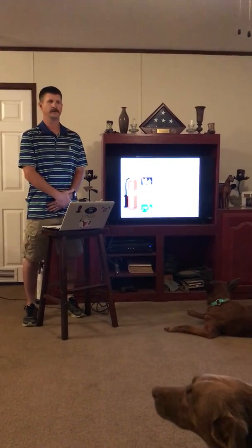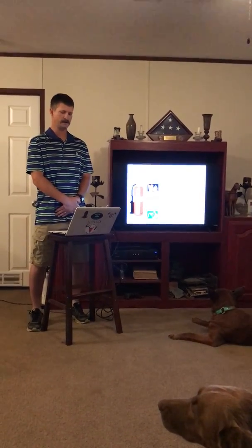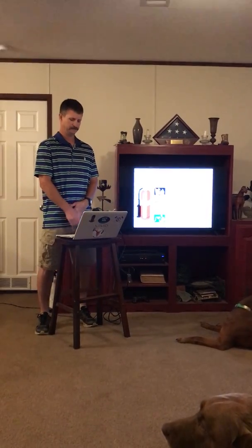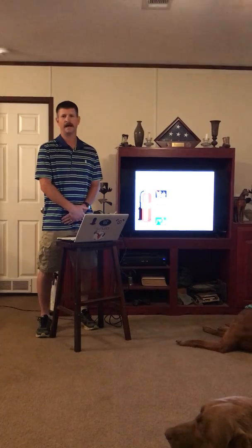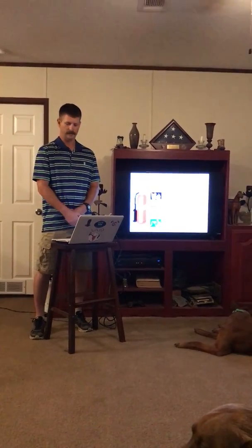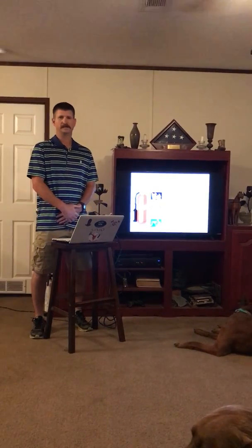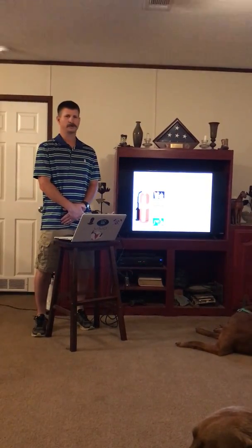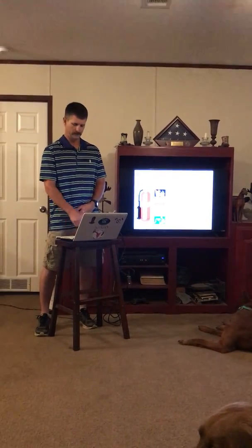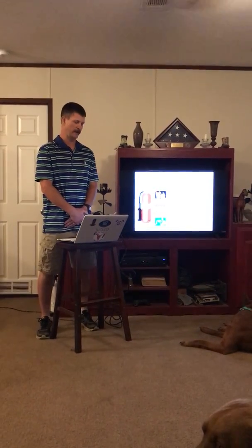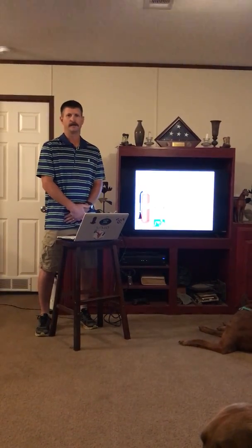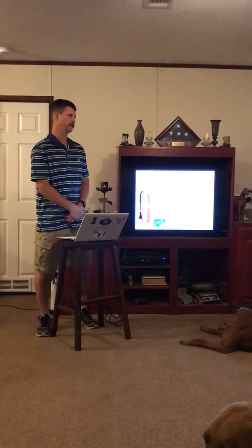The next type is going to be your CO2 extinguisher, carbon dioxide. These extinguishers are rated for Class B and C fires. They're going to have 2.5 to 100 pounds of CO2 and 8 to 30 seconds of discharge time. These extinguishers do not have an external pressure gauge where you can visually check them. They're only verified by weight. They have a 3 to 8 foot maximum range, so you have to get pretty close to the fire to be effective.